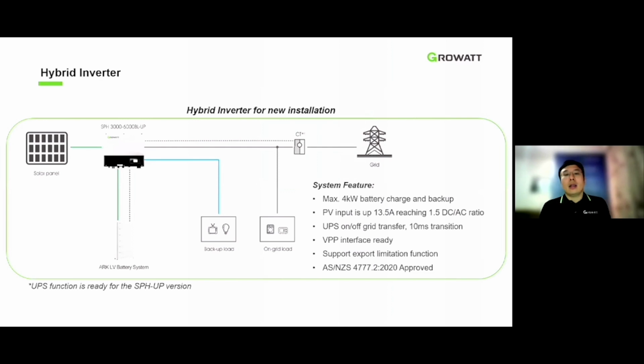Now, another mature inverter of ours, the SPH 3 to 6K UP inverter. This has minor updates from the old SPH inverter. First, we've increased the off-grid load capacity from 3 kilowatt to 4 kilowatt. Also, like our other inverters, the maximum DC side current has been widened to 13.5 ampere, so it works perfectly with large panels.